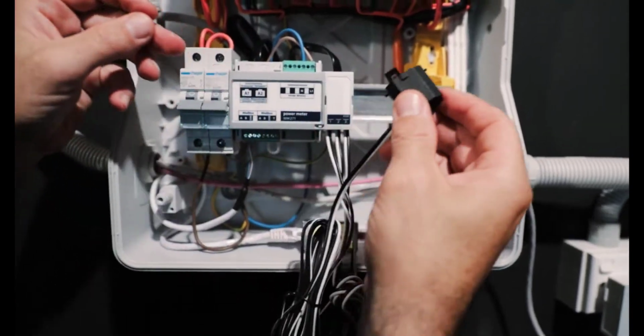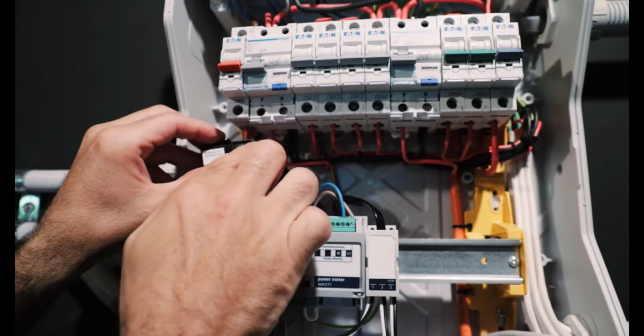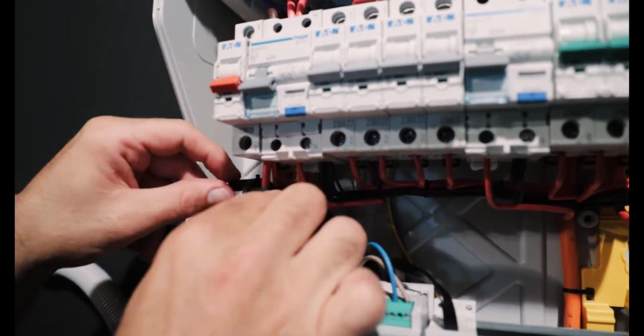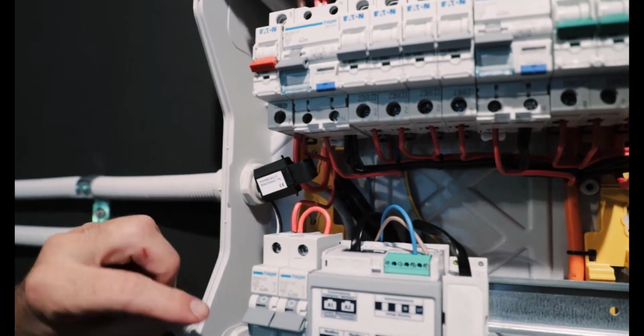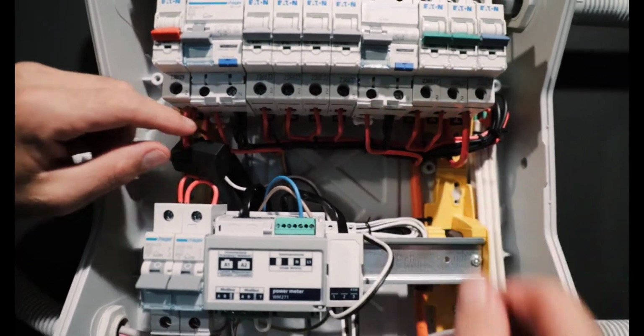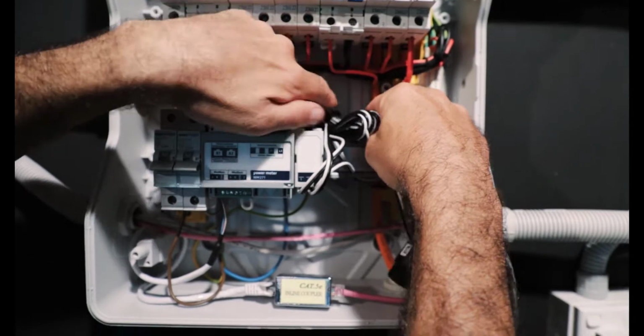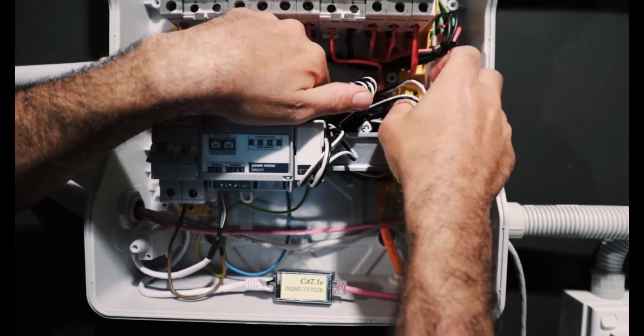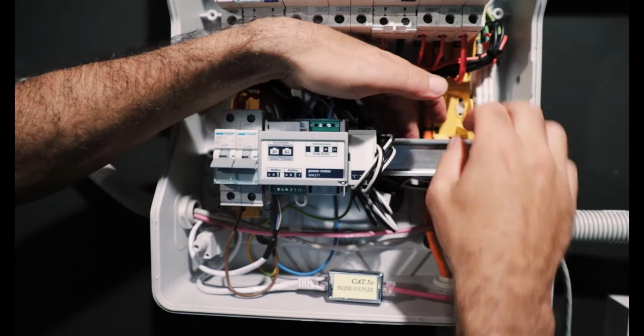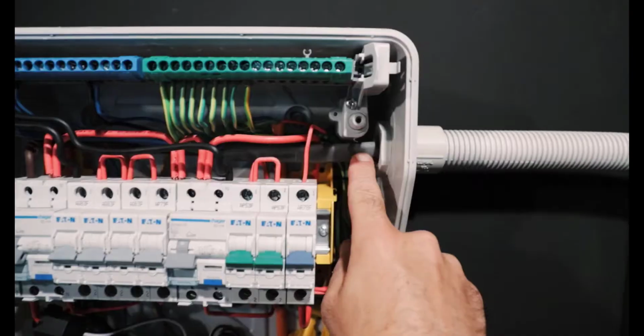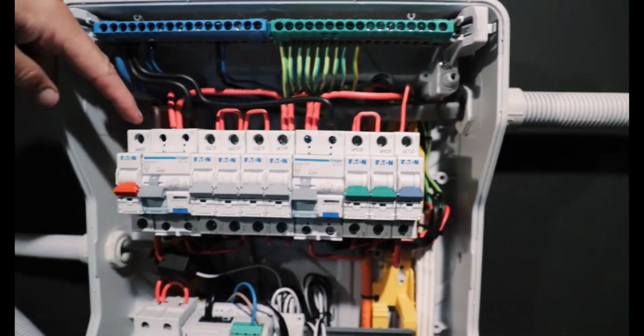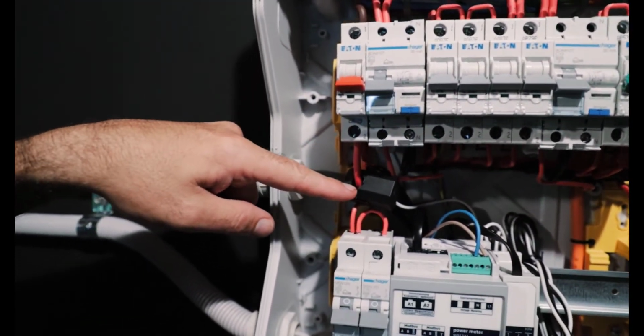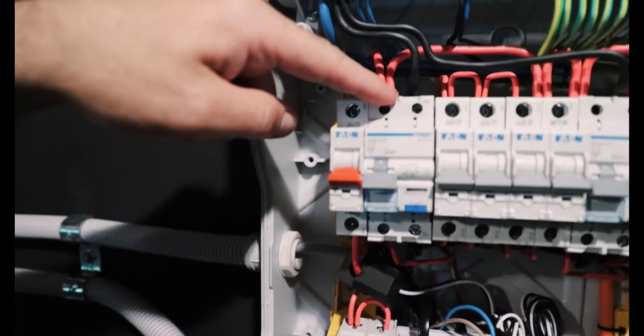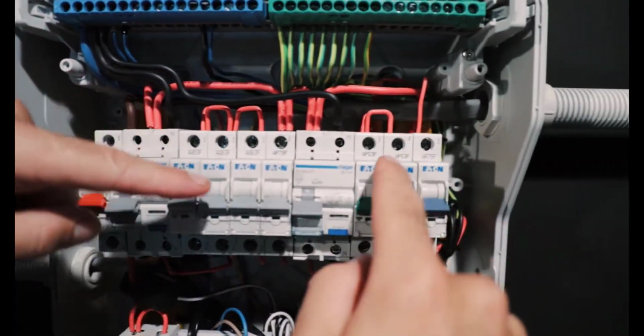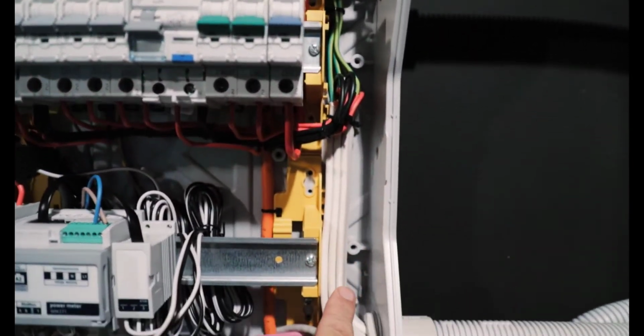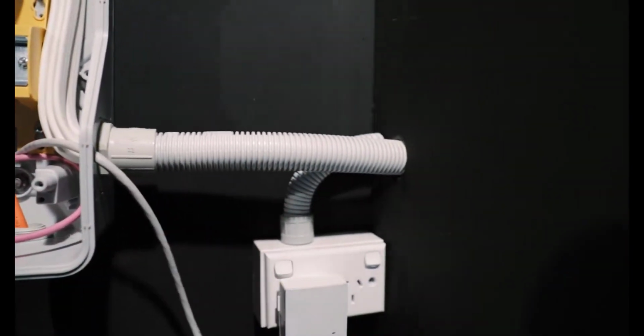And then what we're doing with this one is we're just going to grab it onto the AC going to all of the different loads, and we just tidy up the cables. Now, given that the PV is already going directly into the sonnen system, all we need to worry about on this installation is measuring the loads, measuring the consumption. AC comes in through the main isolator, then from there it goes out to all of the various different RCDs and out to the load circuits. So this is all the load circuits going out, and there we have it.